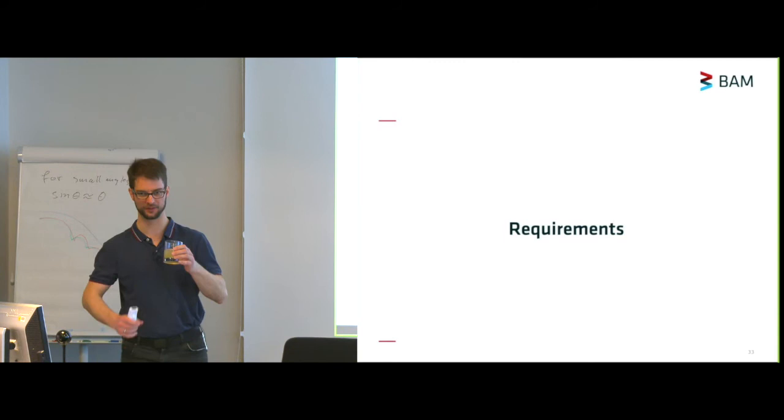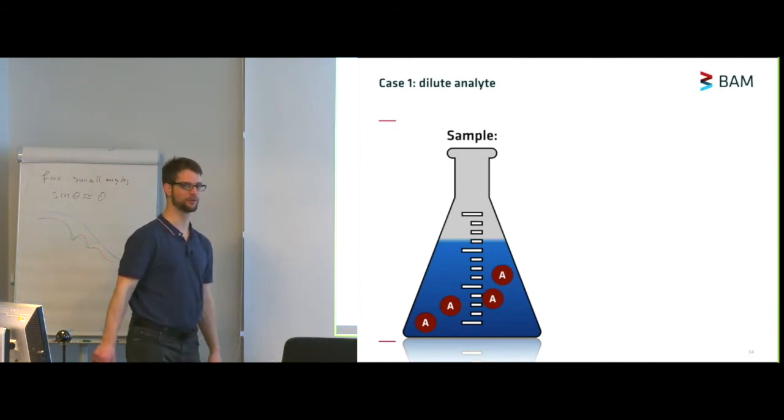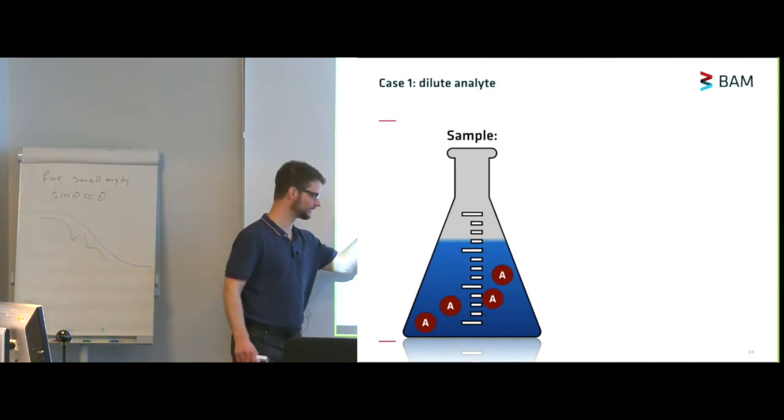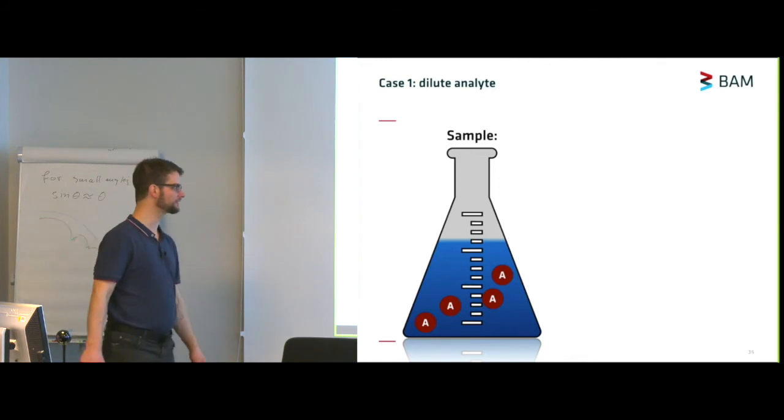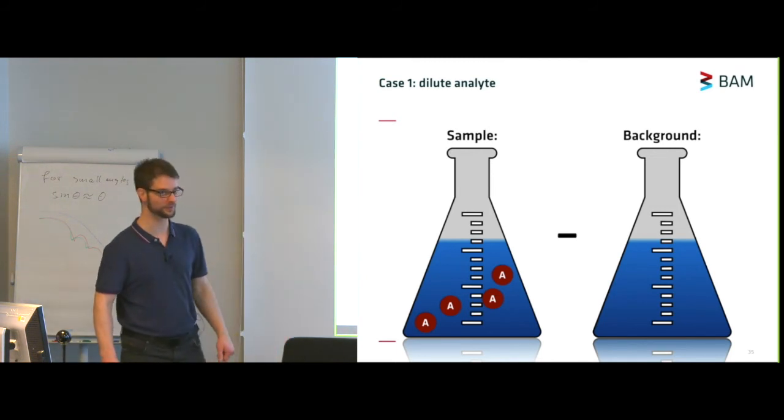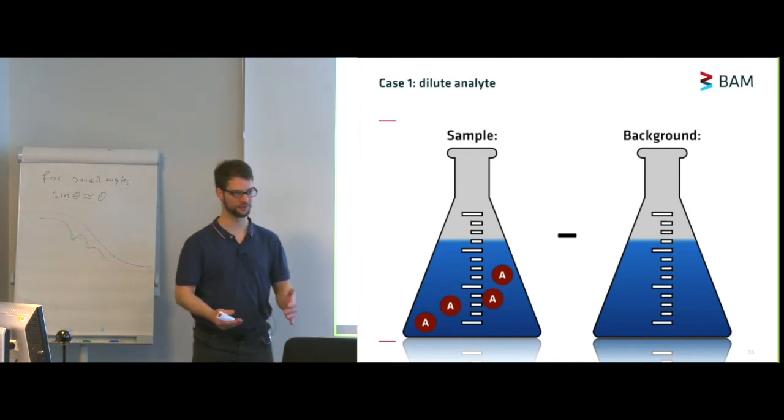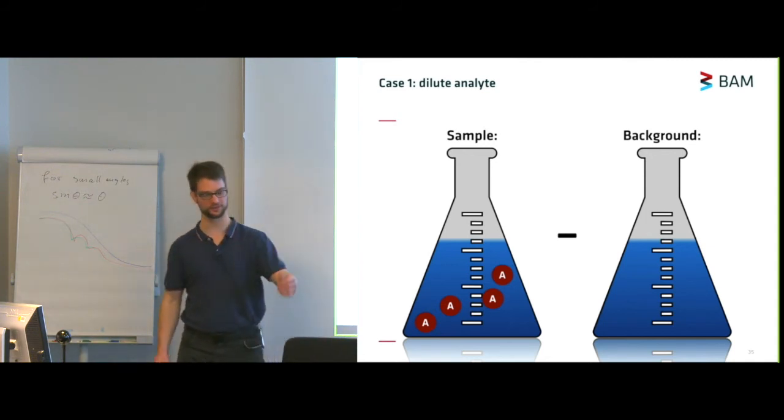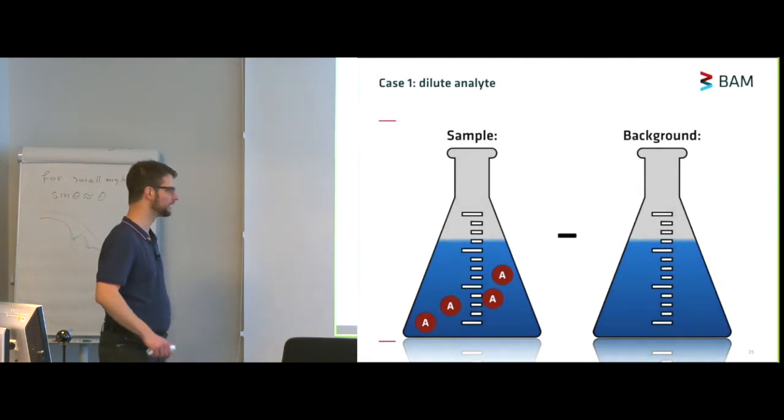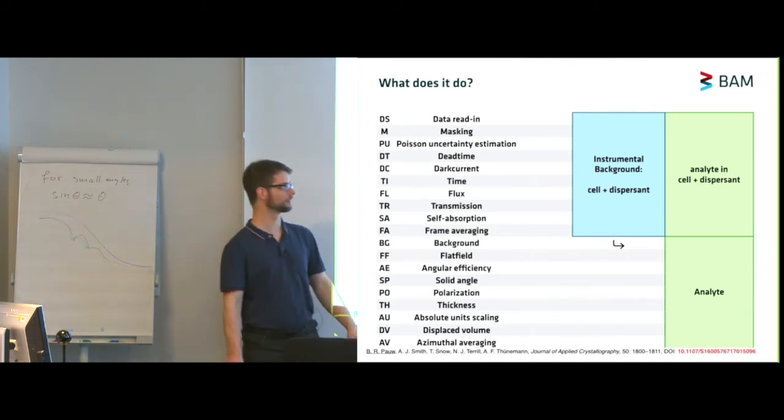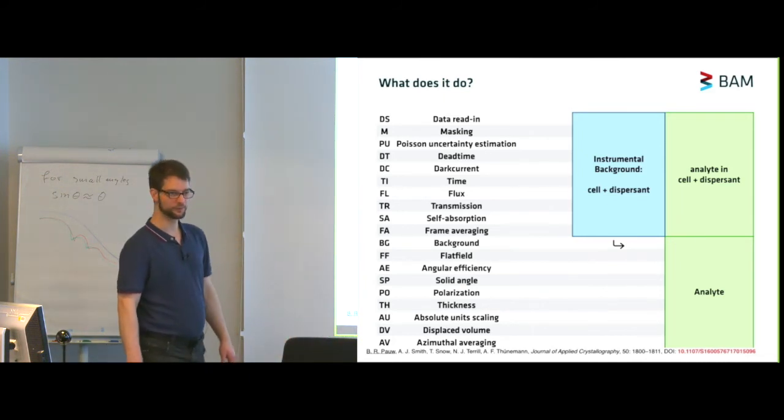So, for these data corrections to work, there are some requirements. First of all, you need to store all your metadata, but the second, and perhaps most important, step in getting well-corrected data is to select a correct background. And Tim already mentioned this a little bit. So, if you have a simple sample, a sample of dilute analyte in a particular solvent, what you would need to subtract is everything except the thing you're interested in. So, in this case, the solvent in its container, in the same container, ideally. So, we have flow-through containers, so that we can always subtract exactly the container plus solvent, compared to the container plus solvent plus analyte.